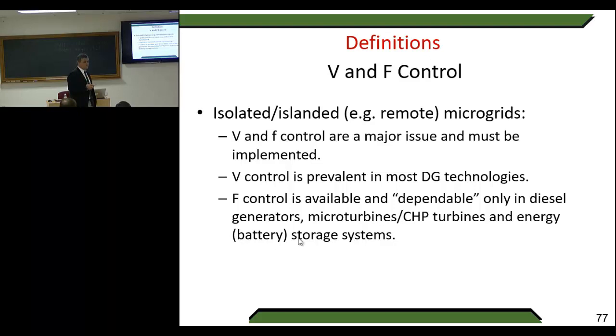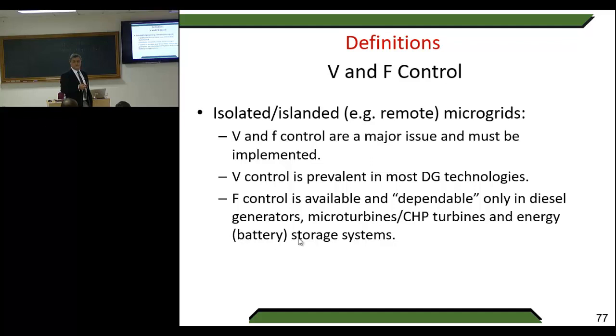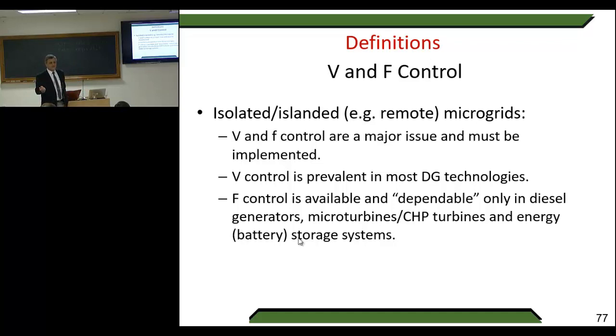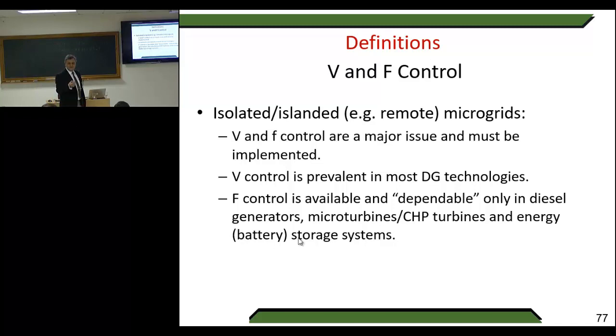Last week in Chile, the first trial by Laborelec/Engie tested frequency control of a 100 megawatt photovoltaic plant with a de-rating of 30% compared with MPPT. The results are very interesting — they support the main grid. We are working with our ISO on this; it is perhaps more common in Spain, but in Chile there are now trials to provide ancillary services. Of course you lose energy, but if you can avoid a backup system, it is a great solution and the cost is justified.